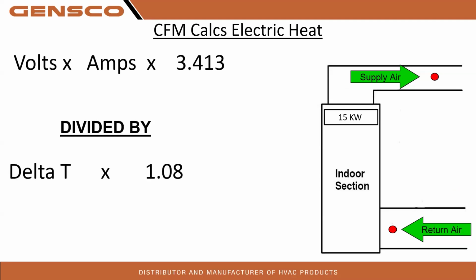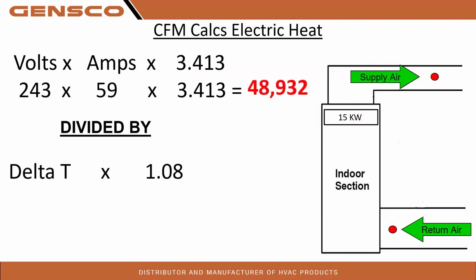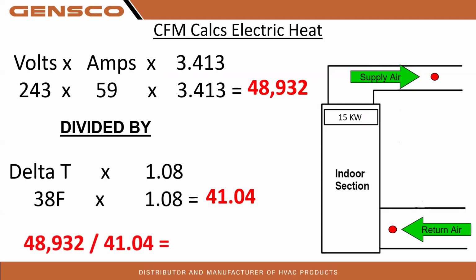Excuse me. So again, this is CFM calcs with the electric heat. You got 15 kW, you got volts times amps times 3.413. So we're pulling actual 243 volts. We have 59 amps total to that 15 kW times your 3.413. We have 48,932. So we get divided by the delta T. We got a 38-degree temperature difference times the 1.08 altitude factor, 41.04. 48,932 divided by 41.04 does 1192 CFM.